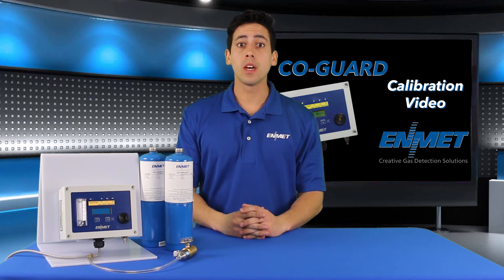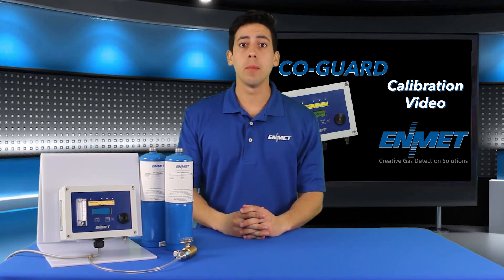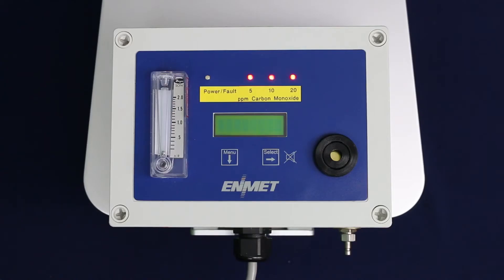In this video I'll be walking through how to calibrate ENMET's CO-GUARD. To be able to properly calibrate this unit, you must wait three to four hours after initial power-up before starting the calibration process.